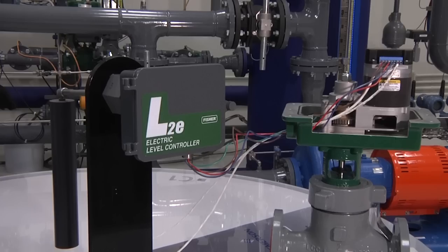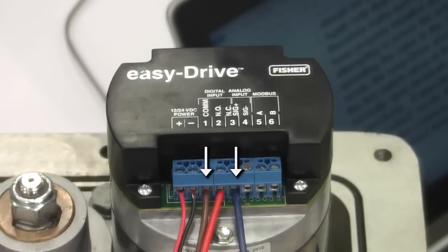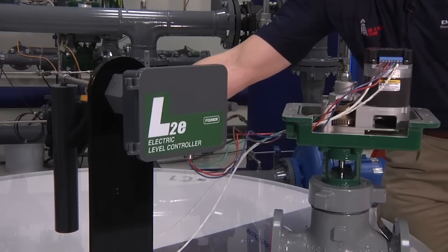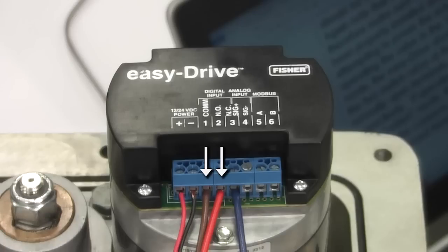Notice when the controller is not activated, terminals one and three are in continuity and the valve is closed. For this example, we will trigger the easy-Drive by activating the L2E. Once the L2E has been activated, continuity is made across terminals one and two, and the valve begins to open.